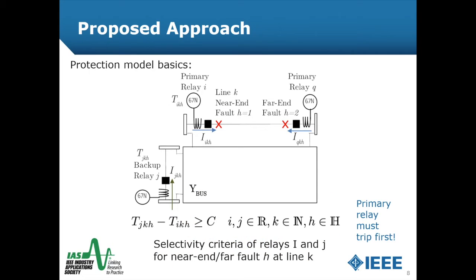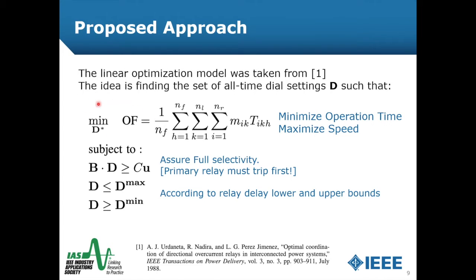This figure shows the fundamental basics of this model, where we have two primary relays that successfully trip when a fault occurs between the near-end and the far-end. This tripping must satisfy the selectivity criteria constraint, where the primary relay must trip first. The objective function of the proposed approach is defined as a minimization problem based on the average sum of operating times of all primary relays for two fault locations: the near-end and far-end under consideration.